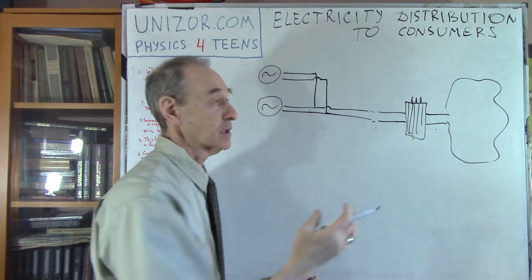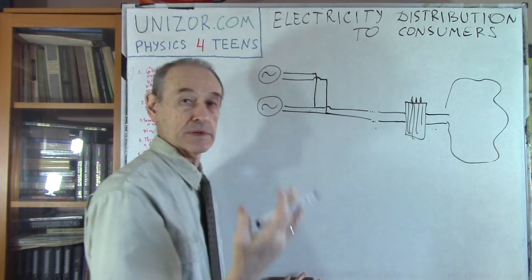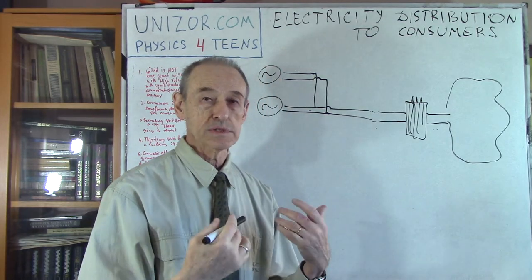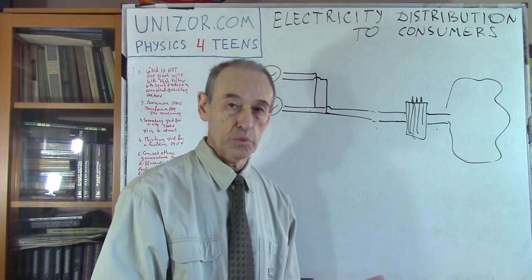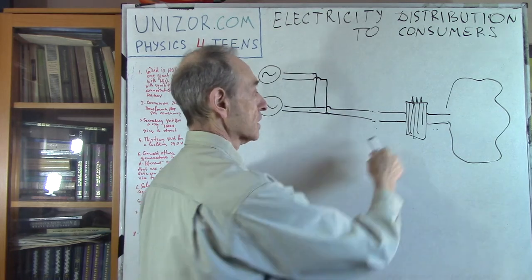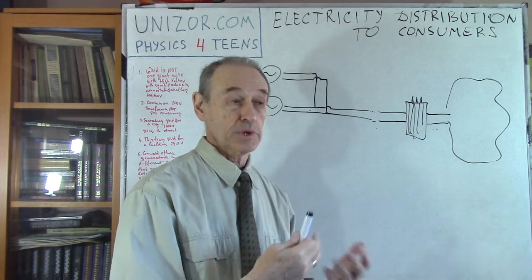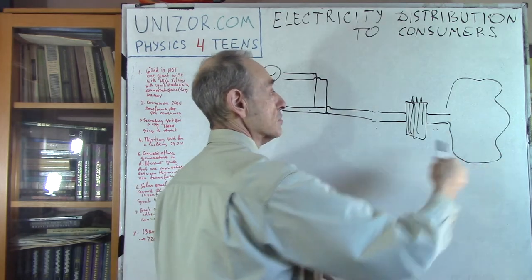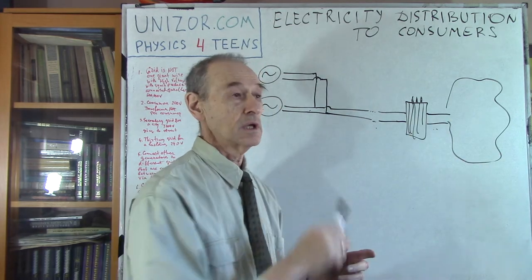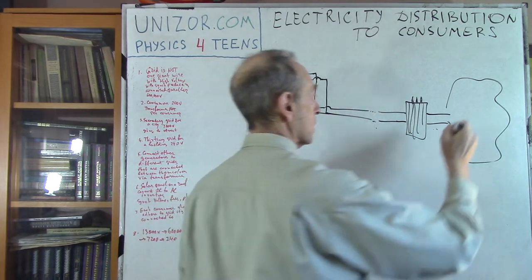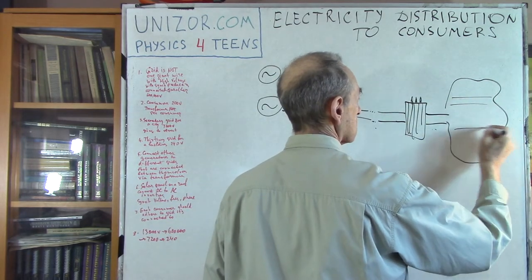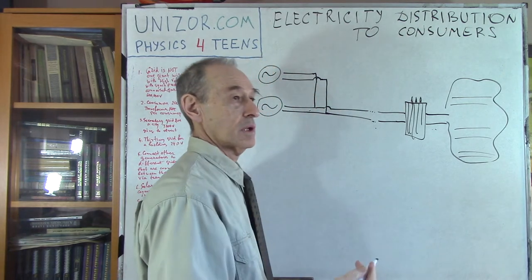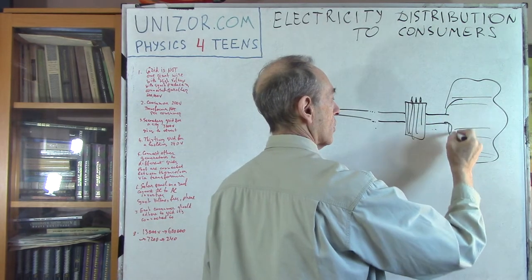Within the city we have already lower voltage and higher current. But these are smaller distances, so we can think about what is the most economically viable way — what kind of voltage is the most beneficial from a cost perspective. Then we can distribute it in the city along the streets. You have one street, another street, and another street.